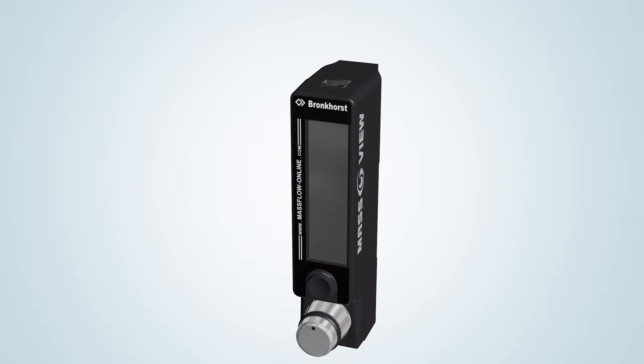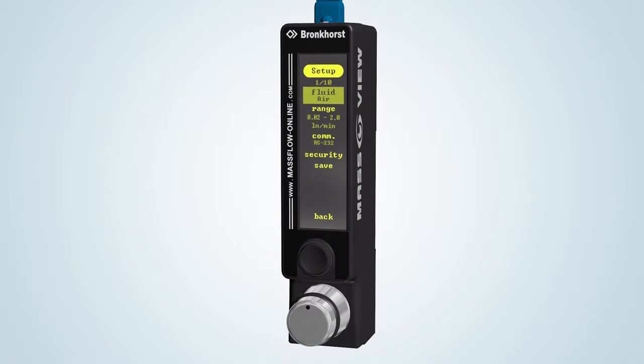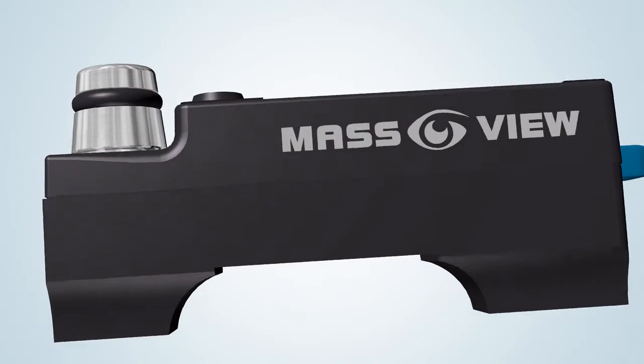This thermal mass flow instrument is supplied with 15 to 24 volt DC. After power-up for the first time, the multifunctional OLED display shows a setup. This menu allows you to select main settings for your process. Press in the center of the four-way button and navigate to the fluid name using the up and down direction. Press in the center once again to make a selection. Subsequently, the flow capacity and communication type are selectable in the same way. These settings will be stored when the Save button is pressed twice. Now the instrument is ready for use.